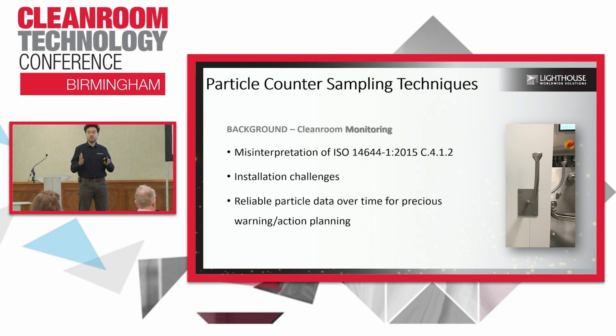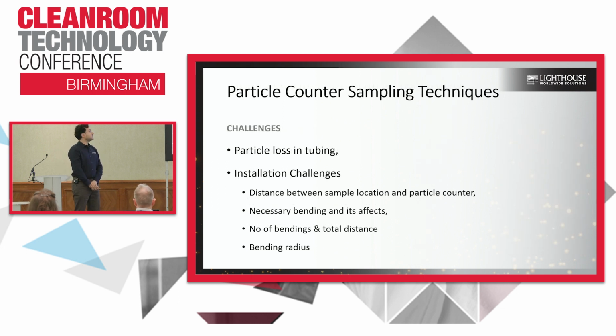The reason is simple, because even though we said, okay, this special tubing is not capturing any particles, in fact, due to the temperature change, due to the Reynolds number changing as a flow, we are also capturing these particles within the tubing. So cleaning and maintenance of this tubing is important. So we already described the particle loss in tubing, and there are installation challenges, which I mentioned. There is the distance between the particle counter and the tubing, and the necessary bendings and their effect. This is also heavily discussed within this subject. And how many bends will be fine? Can we bend the tube 2-3 times? What will be the diameter and what will be the radius? So these are the main discussions throughout the technical report.